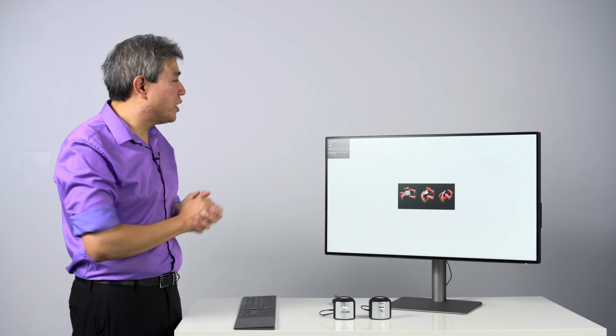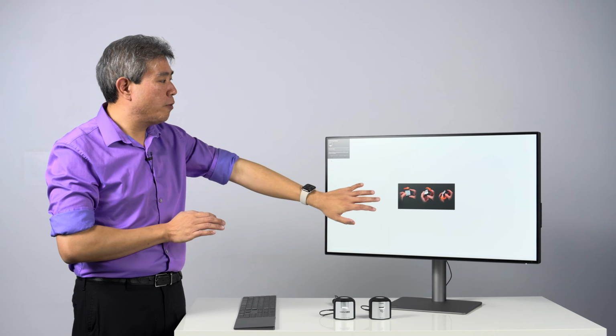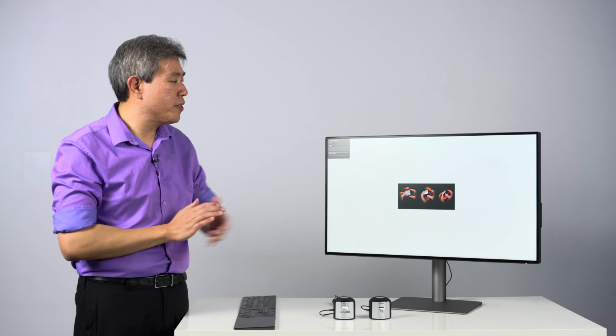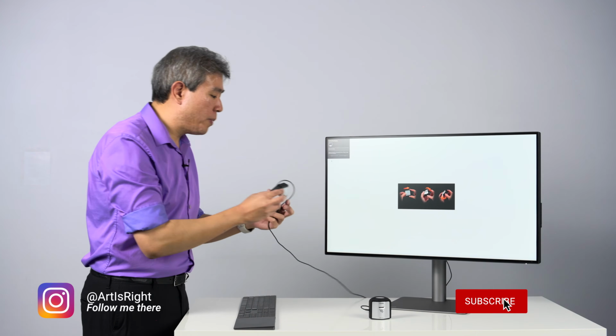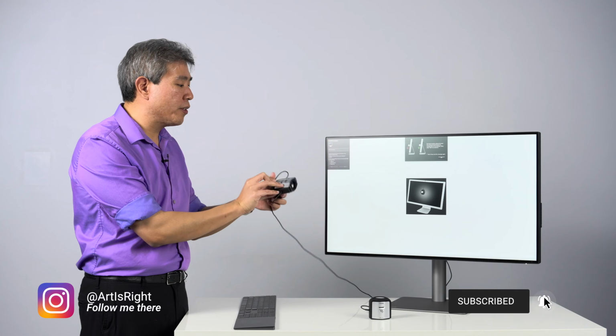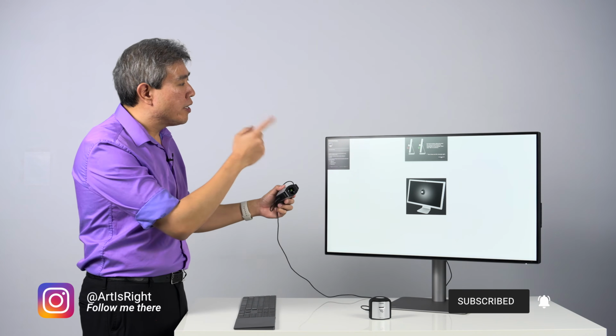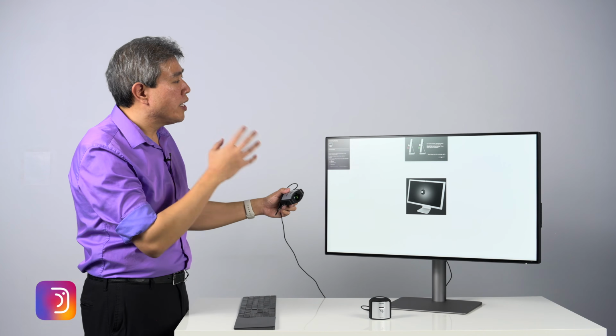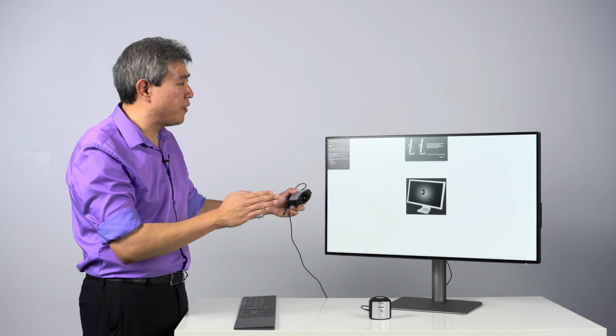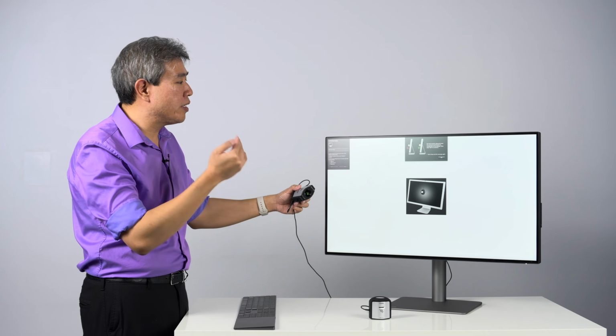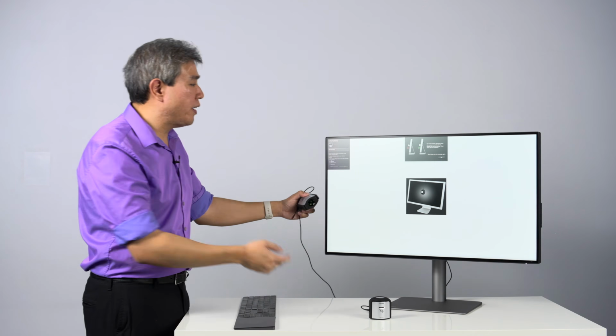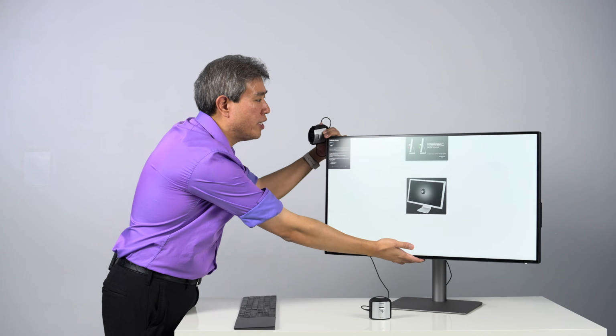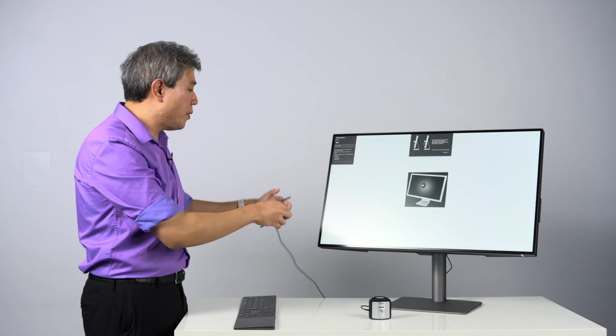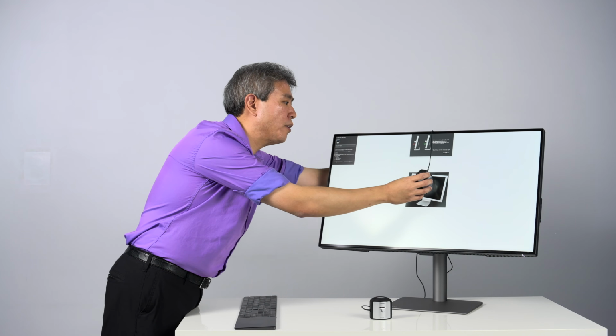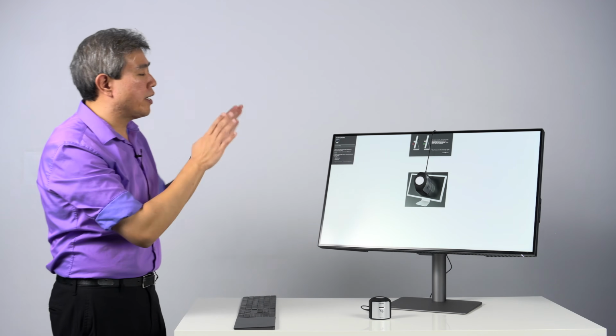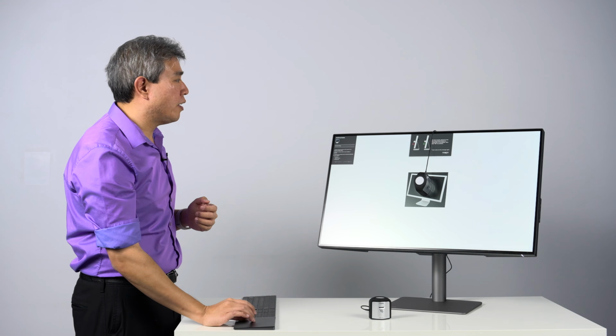Next, I'm at the screen where it's ready to start to do the measurement. Depending on the device that you have, what's showing on the screen may change, but in this case, because I'm using their colorimeter device, it's telling me to pick up the device, pull the cap out a little bit, and swing this over so that the lens is exposed and it can do the measurement. Secondly, a screen will pop down. It's telling you to make sure that the device lays extremely flat on the screen so that there's no ambient light coming in to contaminate the calibration result. What I have found is that the best thing to do when you're running this kind of calibration is to tilt the display backwards like so. This way, when you hang the device and adjust the counterweight on the display, the device will lay flat on the display surface. From here, click on OK.